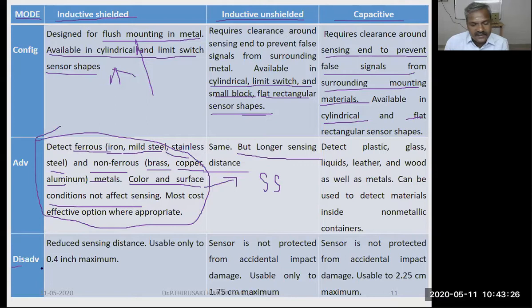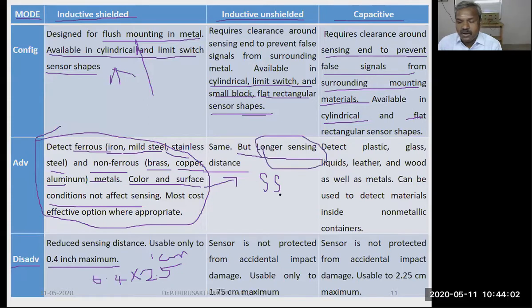The disadvantage of the shielded type is that the sensing distance is reduced, normally 0.4 inches. Since 1 inch is equal to 2.5 centimeters, 0.4 inches is around 1 centimeter, the maximum detectable range. The unshielded can detect up to 1.75 centimeters maximum. That's why I said the unshielded type has a longer sensing distance: here it is only 1 centimeter, and here 1.75 centimeters.